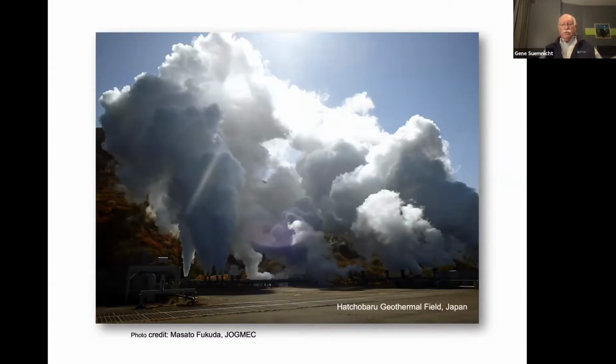And usually in a geothermal system, something like a 50 megawatt power plant is what you're aiming to build. So you need enough wells of 5 to 7 megawatts each to have enough steam to power the plant. And that means you're looking at somewhere around 7 production wells. And then you're also going to have to consider injection wells, because you're going to condense the fluid and put it back in the ground. And then you might want to drill a couple of makeup wells, just in case one of them winds up not being productive, or production changes, so that at least you're not left without a sufficient volume of steam to produce electricity.